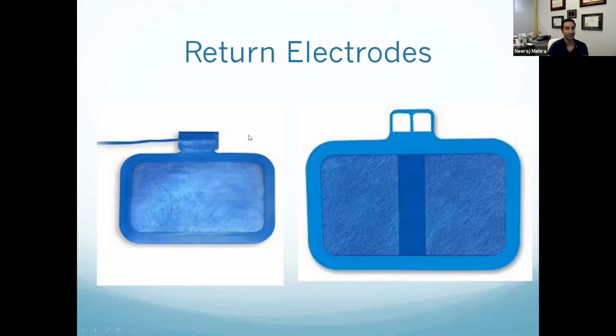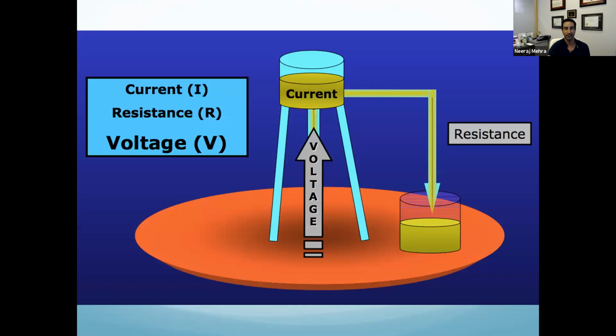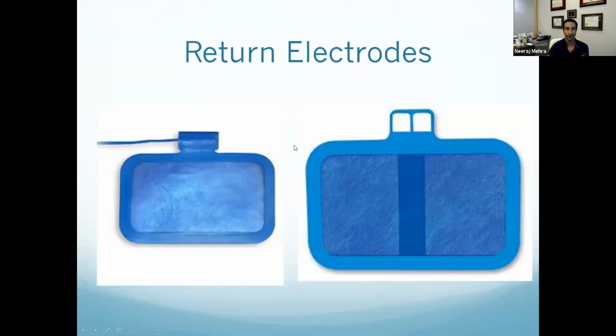I want to take into account how much electrosurgical energy is going through the circuit. So I want my return electrode, which is capturing the electrons, and in our water analogy, something here that's capturing the water coming through and creating a circuit. It's going back and forth, so you don't want much of it leaking out. So return electrode is the proper term.